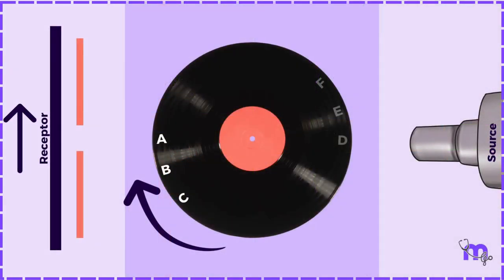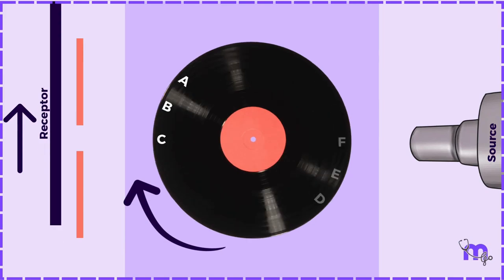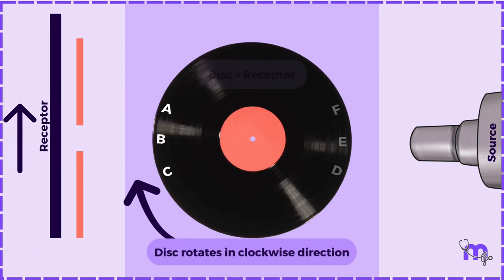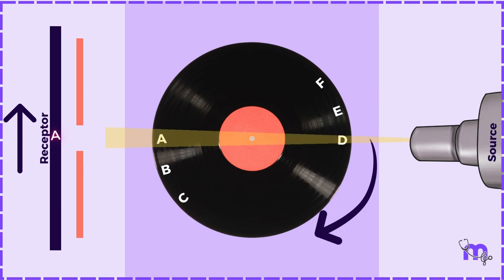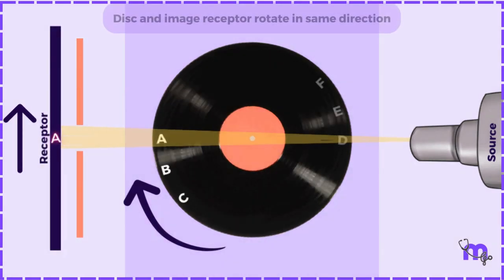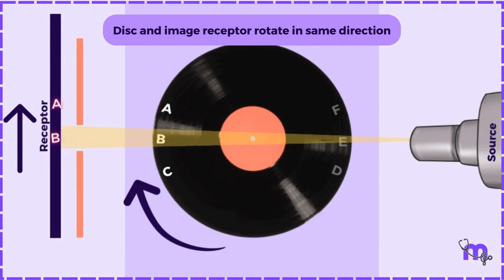Therefore, to solve this problem, let us move the image receptor linearly in the same direction and same speed as the rotating disc, keeping the collimator and the X-ray source steady. Now the disc moves in a clockwise direction and the receptor also moves in the same direction and at the same rate as the disc. X-rays pass through the center of rotation and get attenuated at object A to form the image at a point on the receptor. Similarly, the image of object B forms at another point on the film receptor. Because the disc rotates in the same direction as the image receptor, all the images are sharp and clear without overlaps.